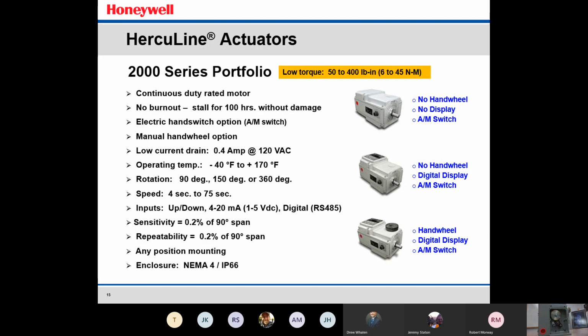The 2000 series, like I said, you have the options on the far right hand side: no hand wheel, no display, auto manual switch. You can get it with the hand wheel, and you can see, if I have my cursor over the top of this actuator, this little knob right here on the bottom left, that would be your auto manual switch. And the hand wheel is the top knob right at the very top, along with the display. So you can see the options that we had talked about on the far left-hand side.